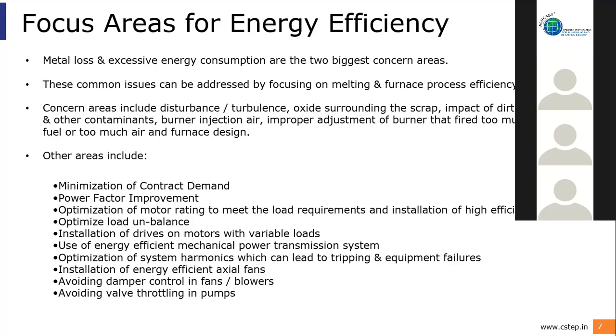Other areas we'll be looking into include minimization of the contract demand. The load profile of the unit will be studied for a 24 hour duration, and based on that load profile, the yearly consumption and the monthly demands, we'll analyze whether there is a possibility of contract demand optimization. Then PF improvement. These days, most of the electricity DISCOMs are billing on the basis of kVAh consumption, and power factor has a direct impact on the energy bills. So improvement of the power factor can directly have a monetary benefit to the units.